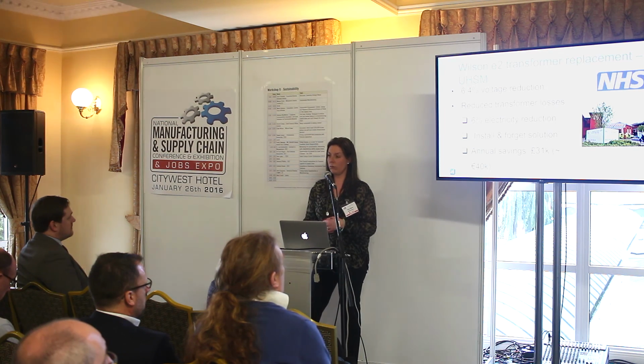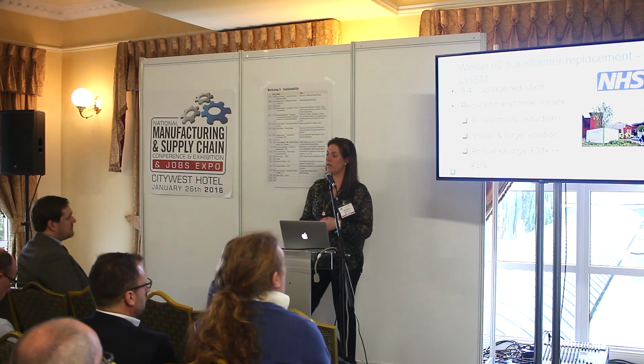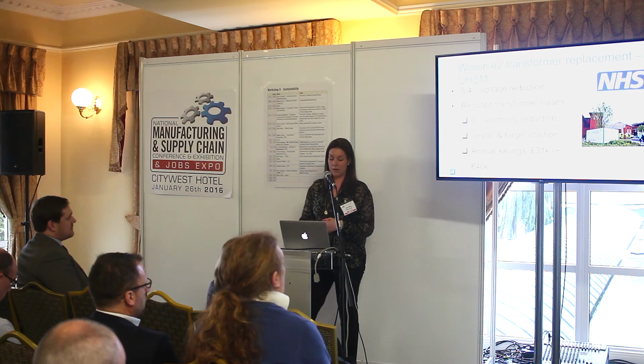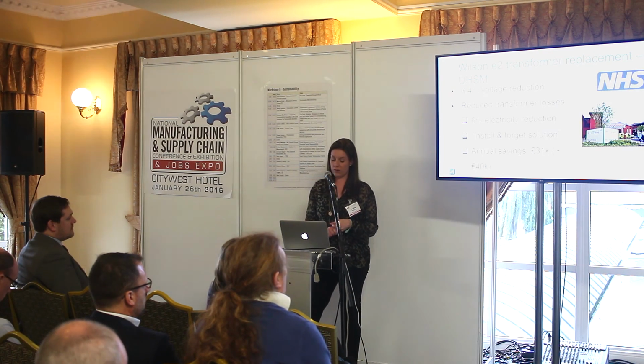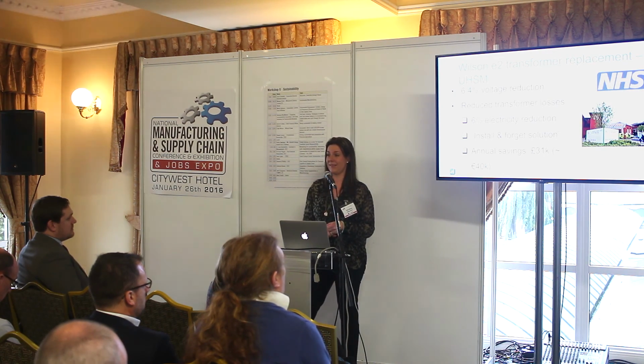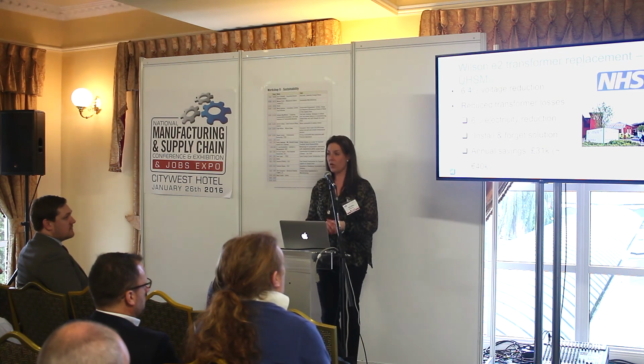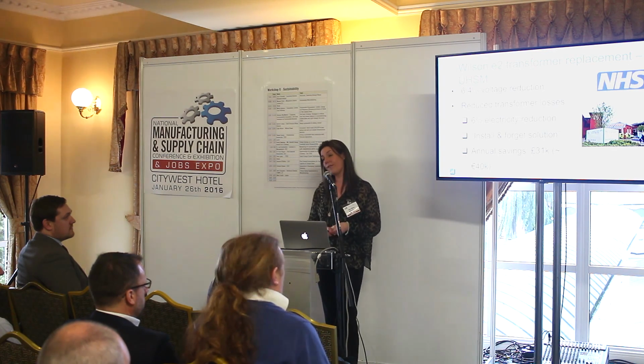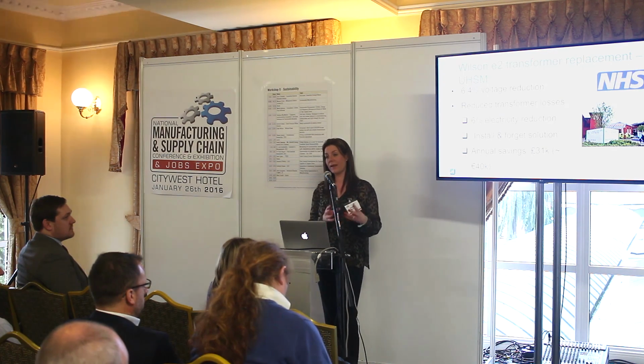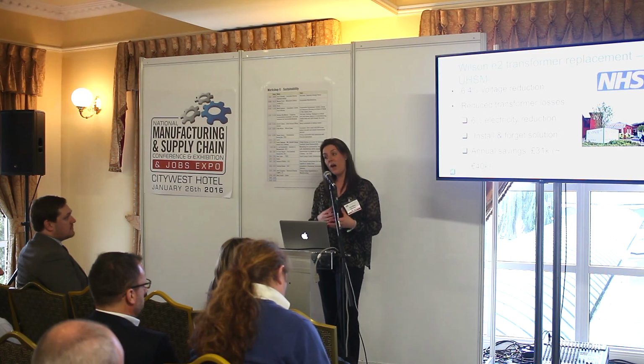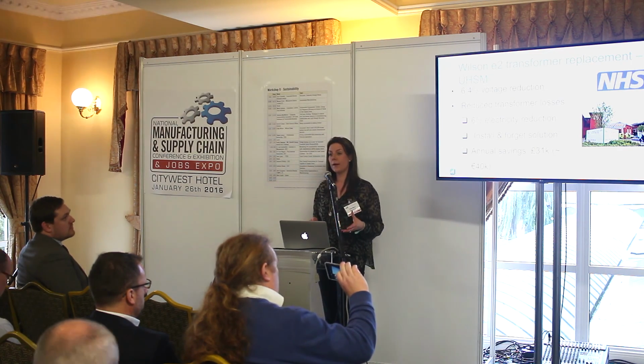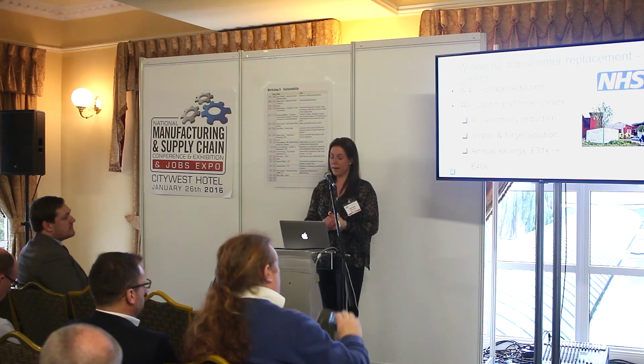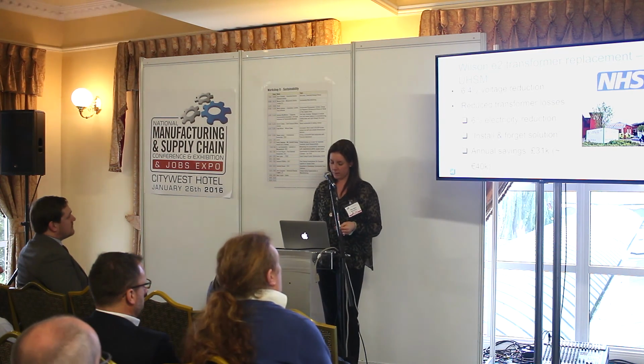And they managed to realise they could reduce the voltage to site by 6.4%. So obviously the losses and voltage reduction meant for them a 6% reduction in electricity. So annual savings of €40,000. And really it's an install and forget solution, because once you've got that capital piece of equipment there, other than taking an oil sample per year, that's it really for maintenance. So it's very low maintenance.